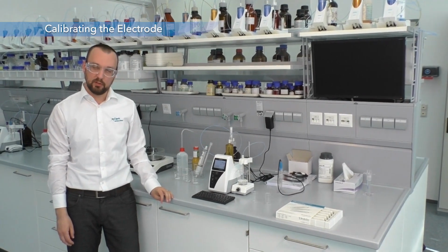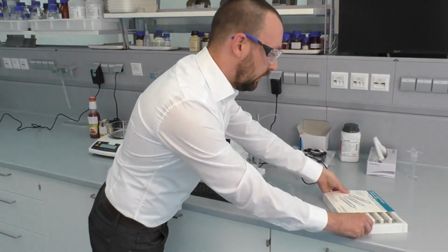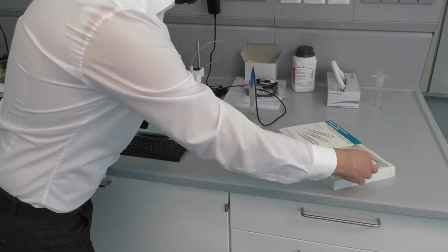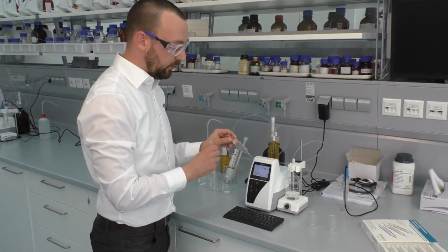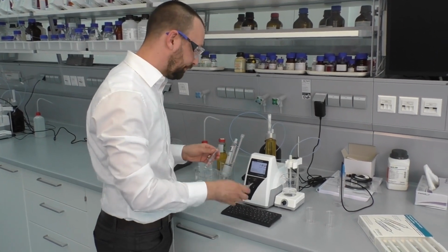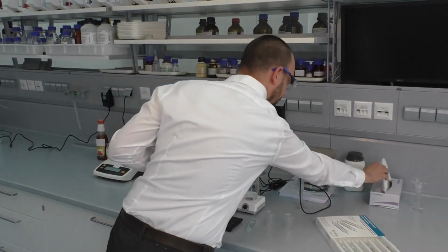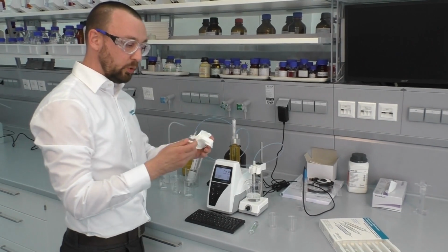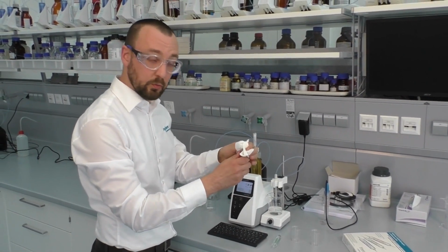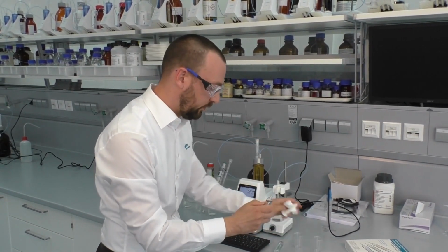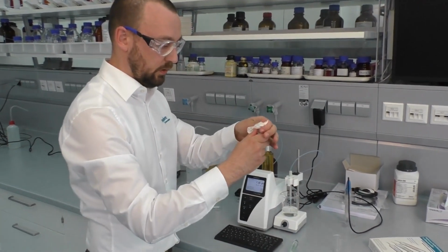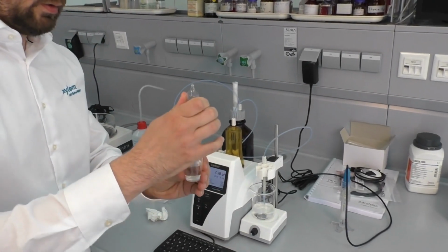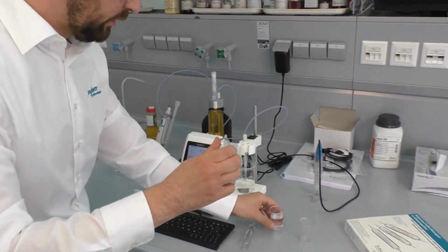As the determination of the total acidity in juices is an endpoint titration, we need the exact pH of the sample. Therefore we need to make a calibration of the pH electrode. To make the calibration, we need buffer solutions. We will perform a 2-point calibration, and we are using the pH 4 and pH 7 as calibration solutions. To open the buffer solutions, we are breaking the necks on both sides. First side, and we can hold the solution into the beaker, and we break the second neck, and the buffer solution flows into the beaker.